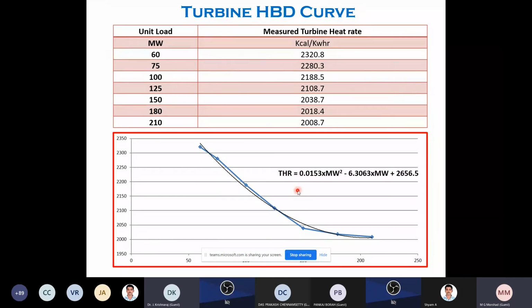I think those who are energy managers in any plant, during PAT cycle 1 and PAT cycle 2, this graph has been given to the BEE as a reference, because on that basis only they can consider it, as our units are not running at full load all the time. So they will consider the heat rate accordingly. Suppose your average load is 180, they will consider this; if your average load is 150, they will consider this. Likewise, the heat rate will vary based on this graph.